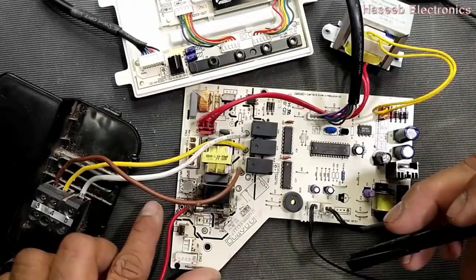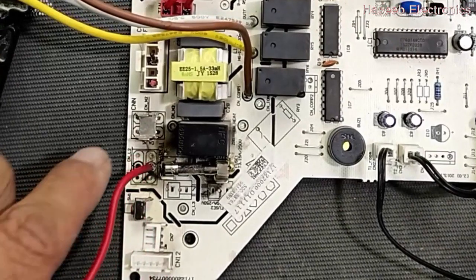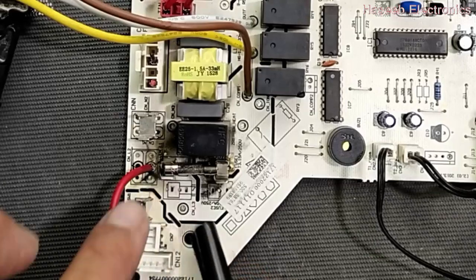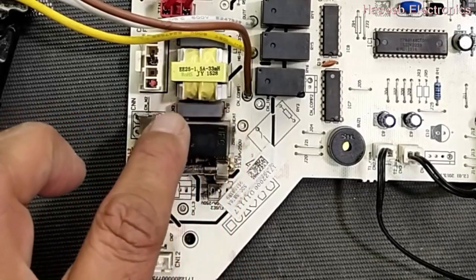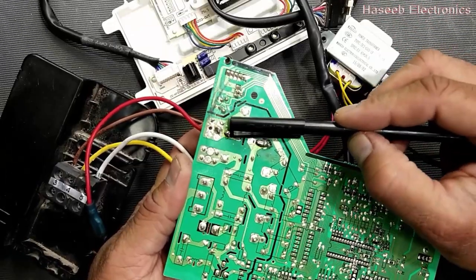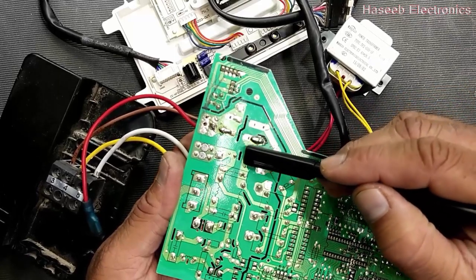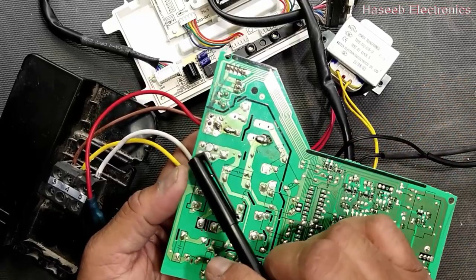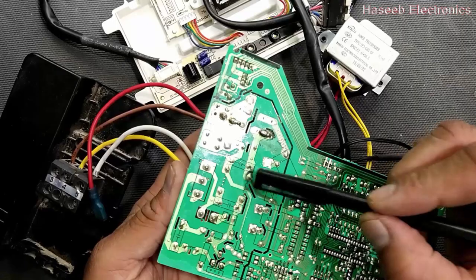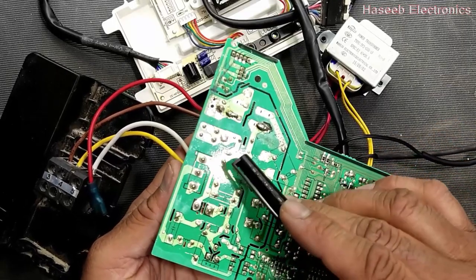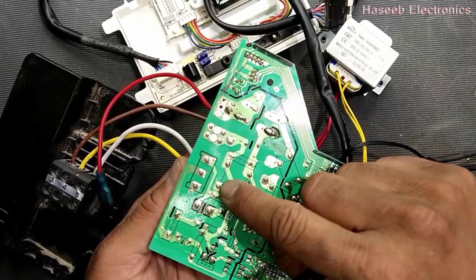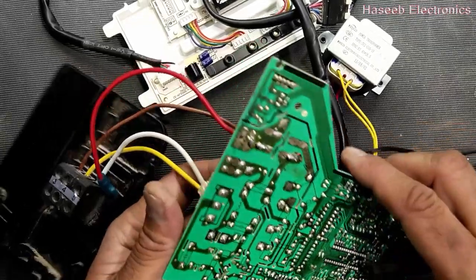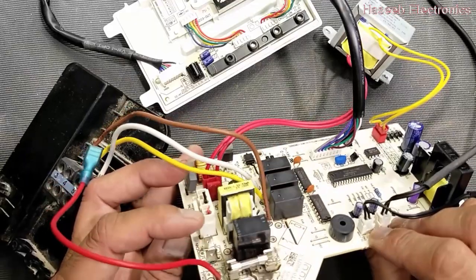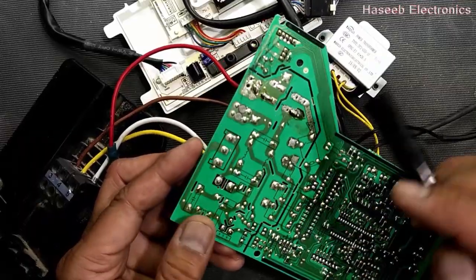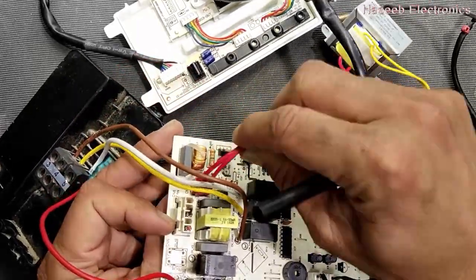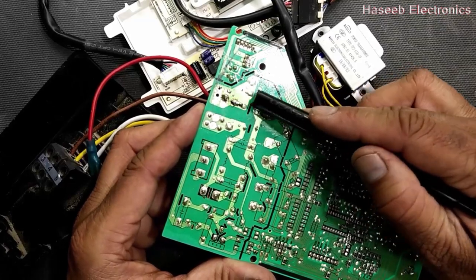Here we have the power input. At this point we have line and neutral. Line passes through this fuse, and after the fuse we have the filter circuit. The neutral comes here. Here we have the filter capacitor, then the inductor, a dual line filter. After passing the filter inductor, we have one line here and one line here. This line is common for the indoor blower fan, and this is the terminal of the capacitor transformer.